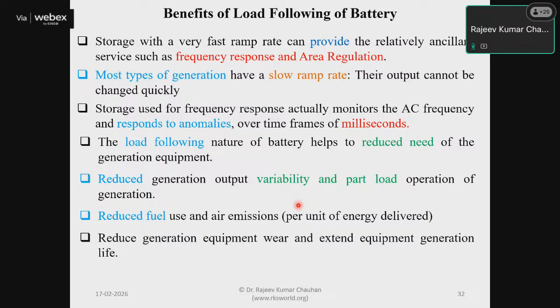Now the benefits of load following by battery. The benefit is that storage with a very fast ramp rate can provide ancillary services such as frequency response and area regulation. Most generation types have a slow ramp rate and their output cannot be changed quickly, as in the case of thermal power plants. So if generation demand suddenly rises by 10 megawatts, a thermal plant may not be able to fulfill it quickly, and at such times we require storage or hydropower plants or other fast response sources.